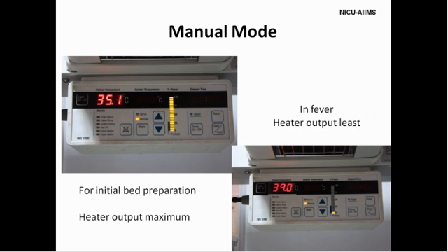Coming to the manual mode. In the manual mode, we directly regulate the heater output by pressing the up and the down knobs. We should adjust this based on the baby's temperature. Remember, by default, the alarm system does not function in the manual mode. Therefore, we should record the baby's axillary temperature every half an hour and then 1 hourly till the temperature is normal, and finally switch over to the servo mode. Unlike the servo mode where both the set temperature and the baby's temperature are displayed, in the manual mode we can see only the baby's temperature.